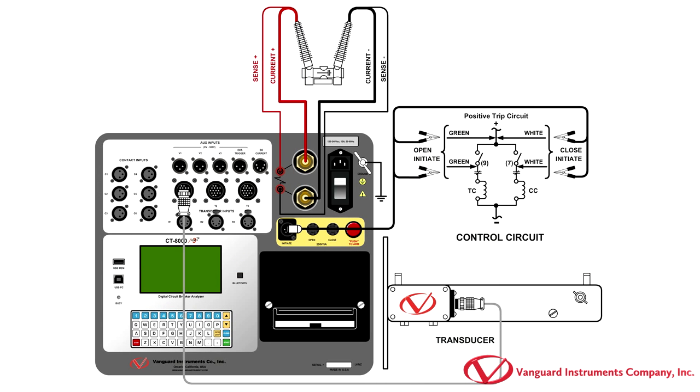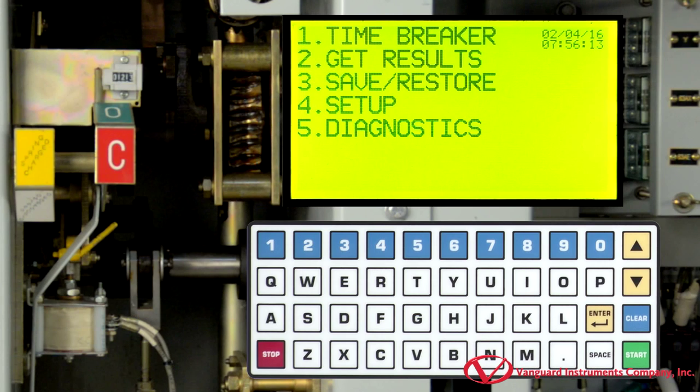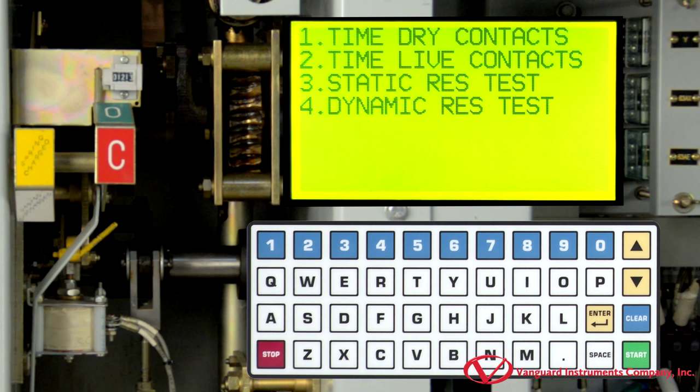Once you have made all cable connections, remove the ground cable from one side of the breaker. To start performing a dynamic resistance test, select the time breaker option from the main menu by pressing the 1 key. Now, press the 4 key to select the dynamic resistance test.